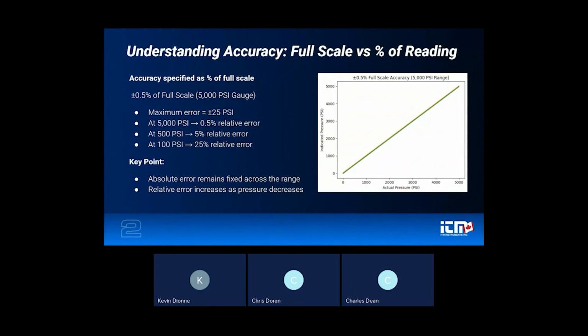So accuracy is often expressed as % of full scale. What does this mean? So for example, if a gauge is specified at 0.5% of full scale accuracy on a 5,000 PSI range instrument, that corresponds to a maximum error of 25 PSI. So how did I get that? 0.005 represents the accuracy in decimal form. We multiply that by the full PSI range. So in this case, 5,000, and that gives you your error rate of 25.